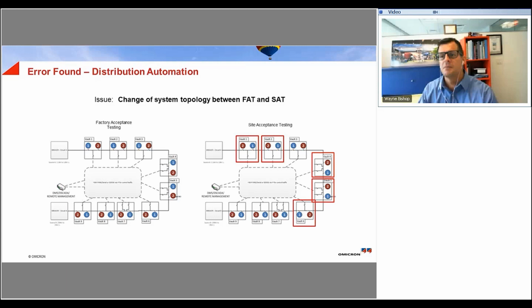The orientation of them sometimes would be switched, and then the relays would also be installed where they were switched. Electrically speaking, I don't think this presents that big of a problem for the switchgear to handle, as the switchgear bus operates purely as a node. However, this did present a problem with the communication-assisted protection with respect to the communication scheme, the fiber communication scheme. The virtual bits had been mapped in such a way, with a specific directionality in mind, and these had to be reworked for the entire process. Without this method of testing, there would be no way for us to really verify that this had been installed incorrectly until an actual event had occurred and the inappropriate switching, if this had been turned on, had occurred.